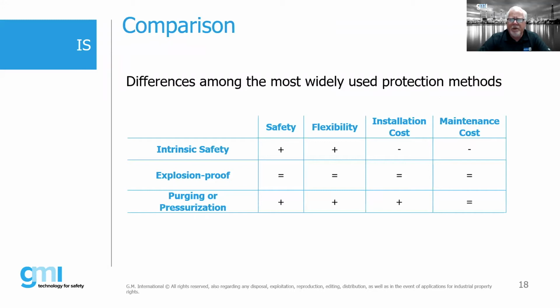So this just gives you a little bit of an understanding of the cost benefits of using intrinsic safety versus some of the other protection concepts. If we look from a safety standpoint, with explosion proof as the benchmark, intrinsic safety is generally a safer concept when it's properly used. Intrinsic safety is allowed in a zone 0 environment if we have IA type barriers in our IA loop. Explosion proof or flame proof we cannot use in a zone 0 area. So there's a little bit more safety built into intrinsic safety.